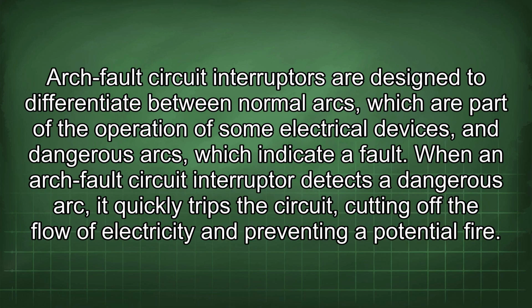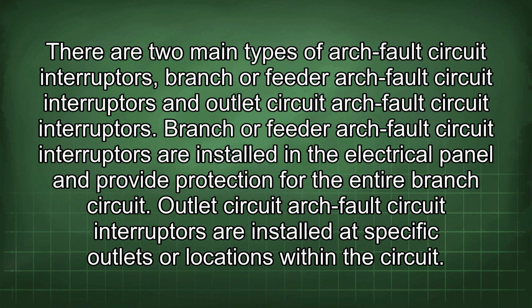Arch fault circuit interrupters are designed to differentiate between normal arcs, which are part of the operation of some electrical devices, and dangerous arcs, which indicate a fault. When an arch fault circuit interrupter detects a dangerous arc, it quickly trips the circuit, cutting off the flow of electricity and preventing a potential fire. There are two main types of arch fault circuit interrupters: branch or feeder arch fault circuit interrupters and outlet circuit arch fault circuit interrupters. Branch or feeder arch fault circuit interrupters are installed in the electrical panel and provide protection for the entire branch circuit. Outlet circuit arch fault circuit interrupters are installed at specific outlets or locations within the circuit.